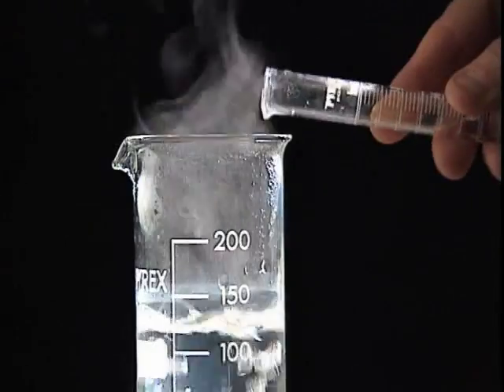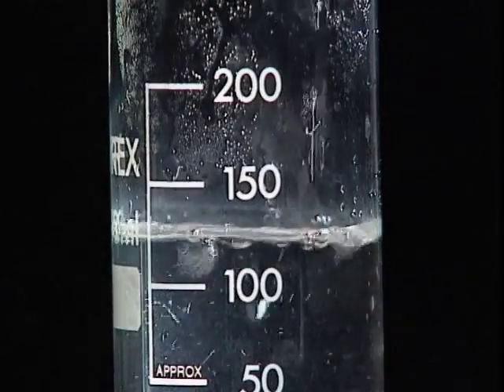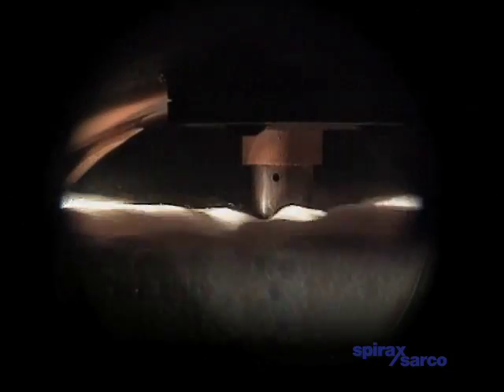As we have seen, many factors can affect this balance. Even at moderate steady loads, feed pump on-off operation causes the boiling rate to be suppressed, followed by a swell which takes the level above the pump-off level. An increase in demand also produces sudden level fluctuations. Furthermore, these effects will compound to produce even larger fluctuations if the circumstances occur together.